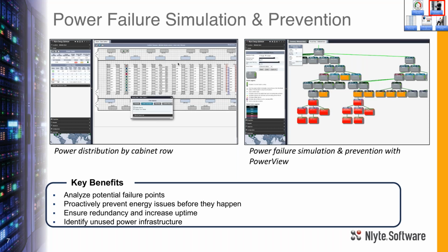One of the unique capabilities of Nlyte is this ability to do what we call power failure simulation. With software, you can simulate a power failure of a particular component and see what the ramifications are to dependent or related systems, and see if you're causing power failures beyond what you were expecting, including any cascading effect. You can do this all with software rather than with your live systems.